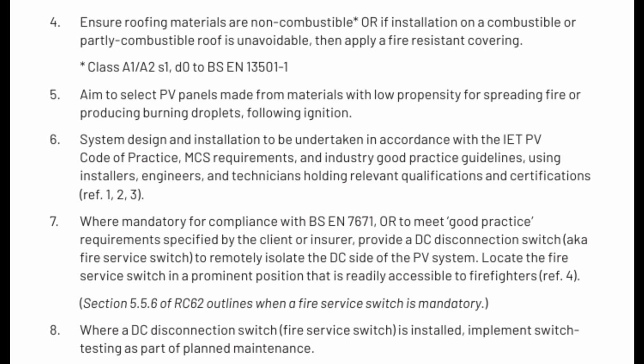Install a DC disconnection switch, also known as a fire service switch. This allows firefighters to quickly and safely isolate the DC side of the PV system in case of an emergency. Make sure it's located in a prominent and easily accessible position. Remember, this might be mandatory based on regulations or your insurer's requirements. If you have a DC disconnection switch, implement regular switch testing as part of your planned maintenance. This ensures it will function correctly when needed.